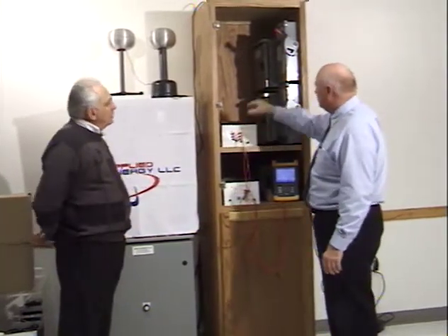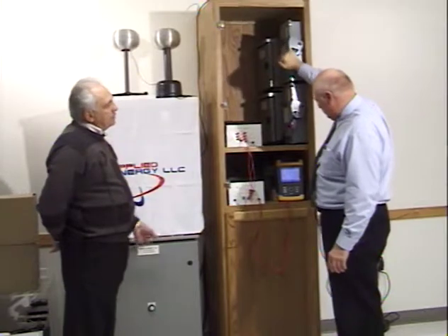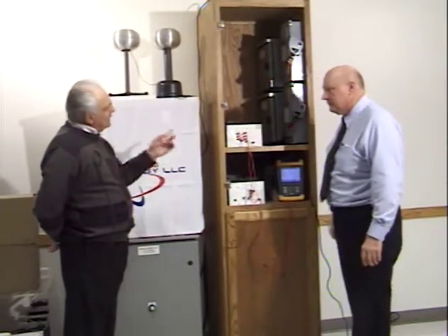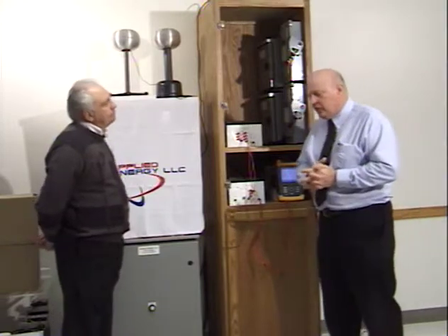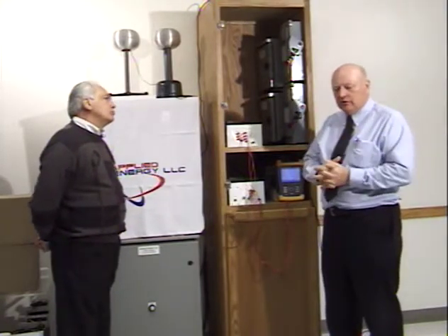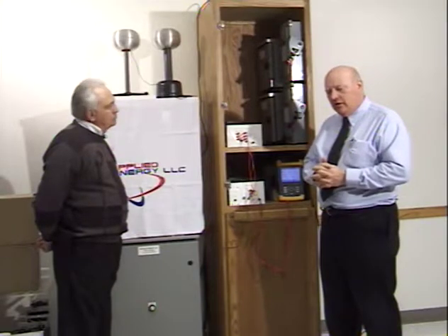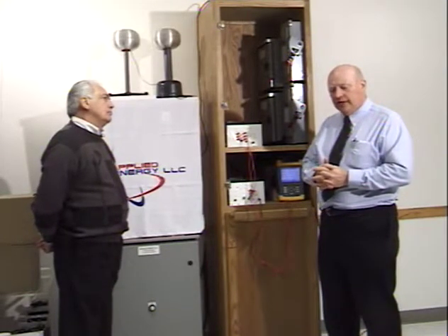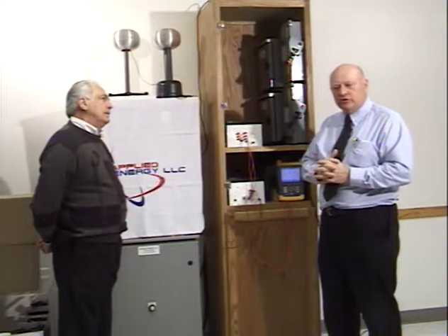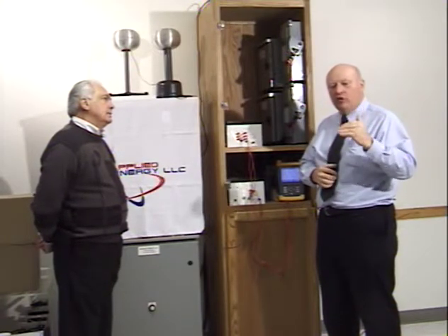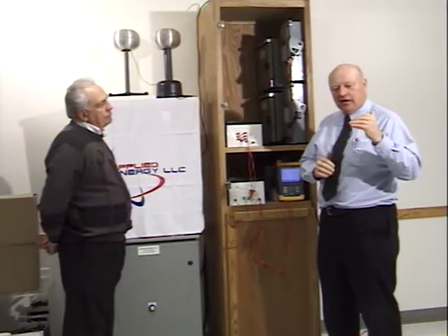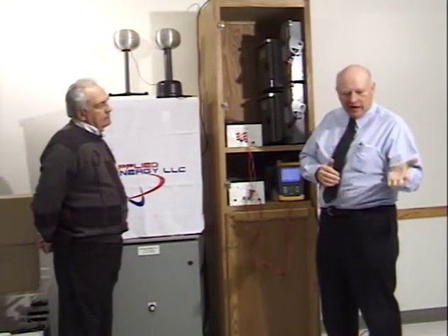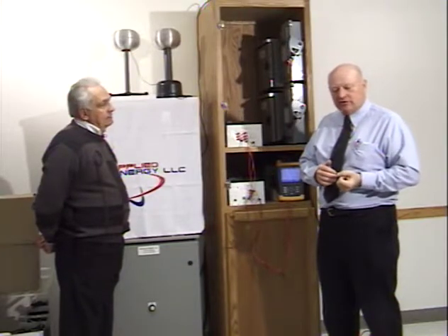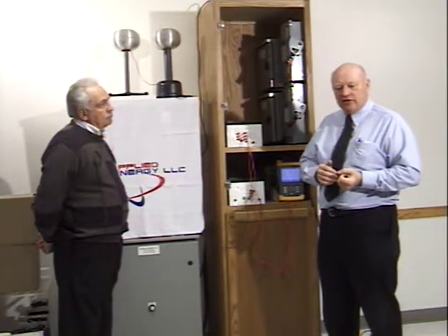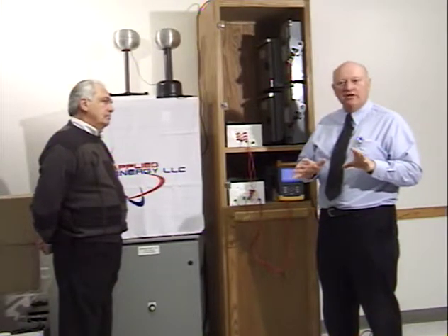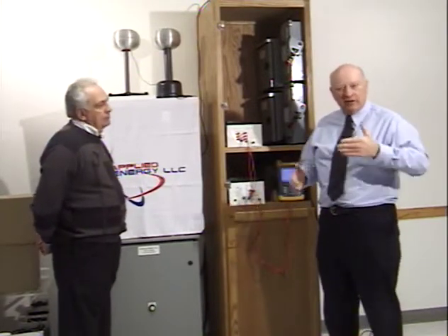Now to go back and ask one question regarding both of these products we've looked at so far, what kind of life expectancy can we get out of these? Well, let me talk just for a second about typical surge suppression for a minute. Typical surge suppressors can handle a pretty good voltage spike, but as they see spikes below their clamping voltage over time, it'll actually degrade their metal oxide varistors or their solid state components. That was one of the reasons we decided to have no solid state components whatsoever used in any of our products. They degrade over time.